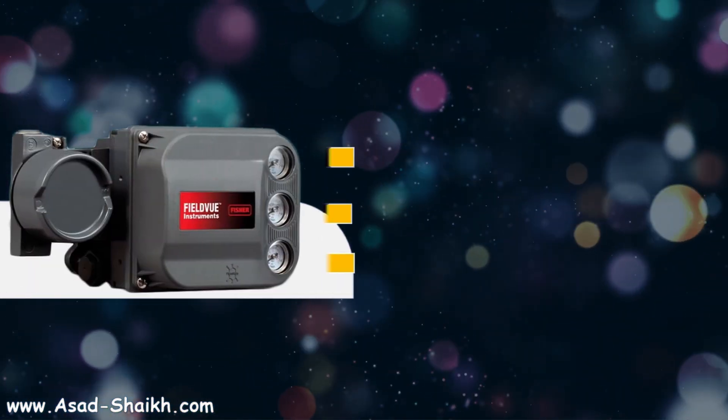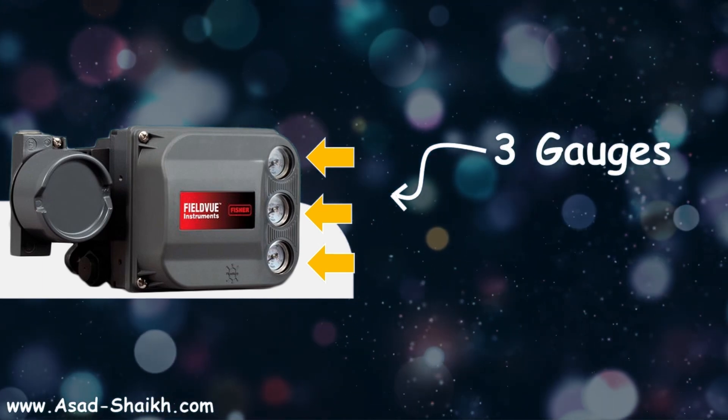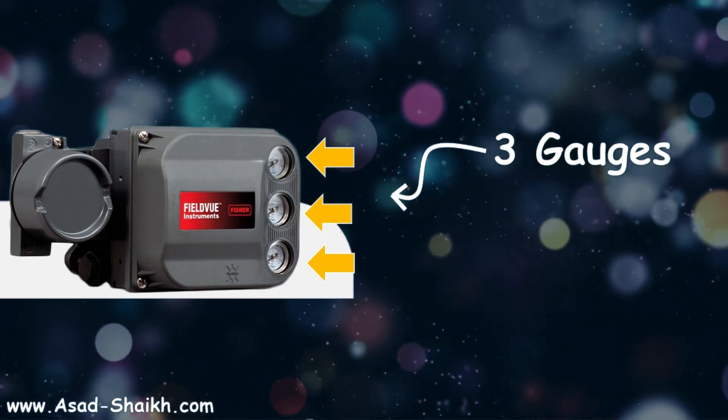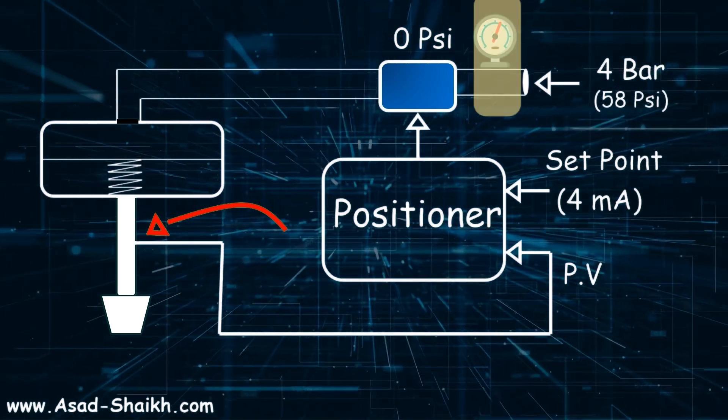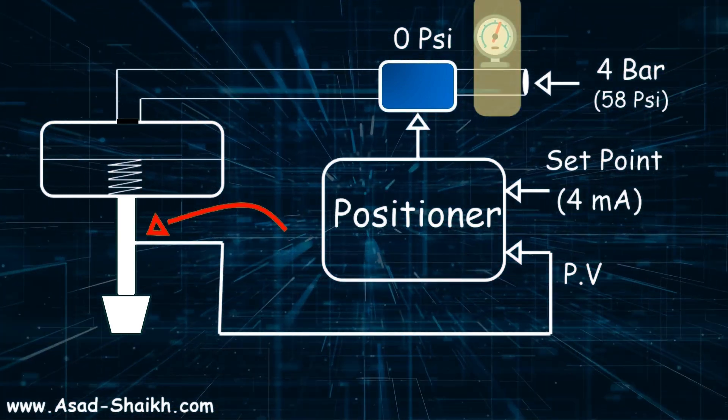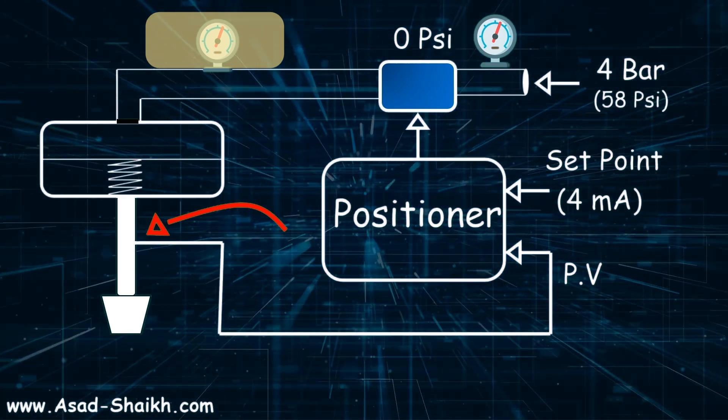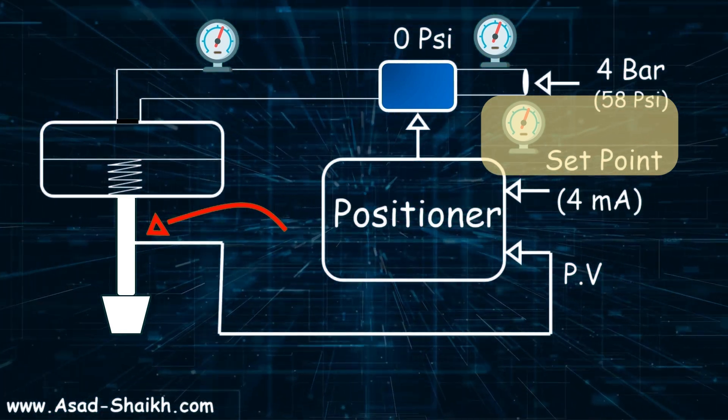But still we have not answered the initial question: why are there three pressure gauges usually available? The answer is because it will help you to troubleshoot what is the issue with control valve. One gauge is put near the air supply so you get to know whether the air supply is available. The second gauge is generally put at the output of the positioner, and the other gauge is put at the set point related to the bench range.